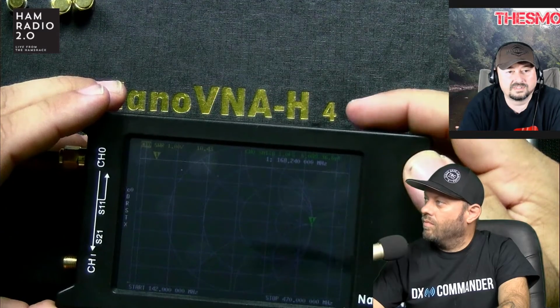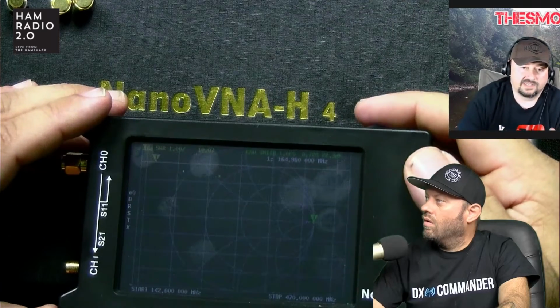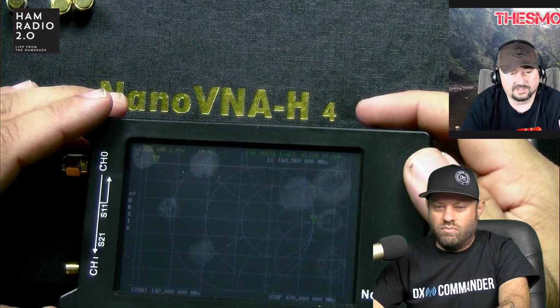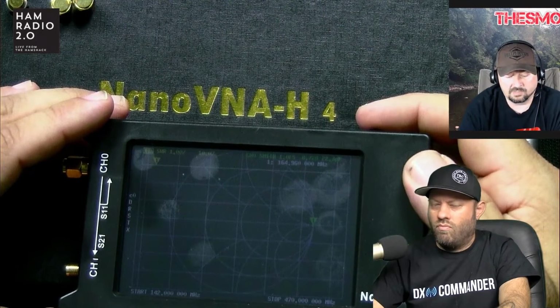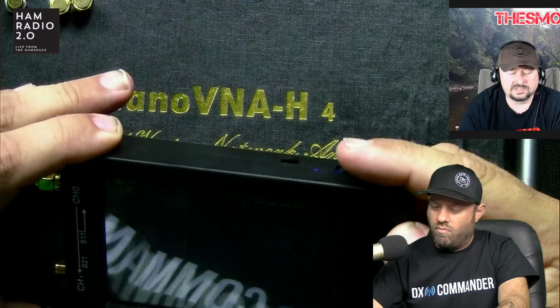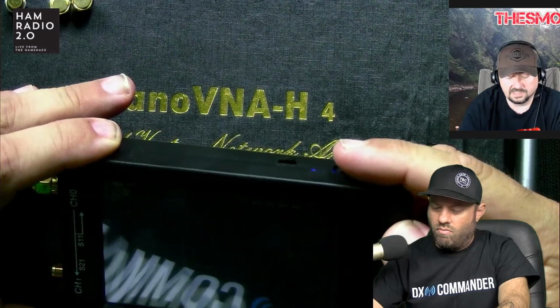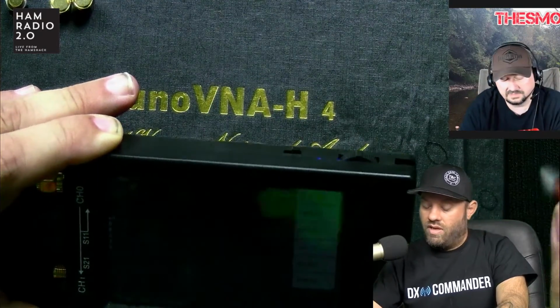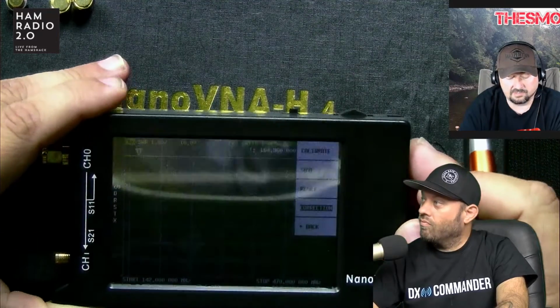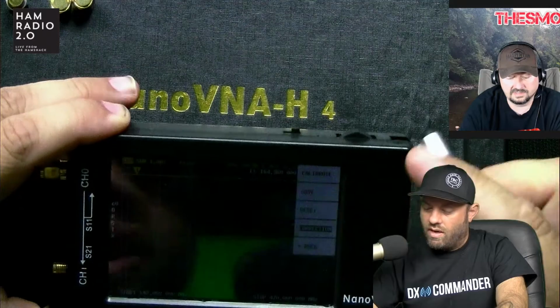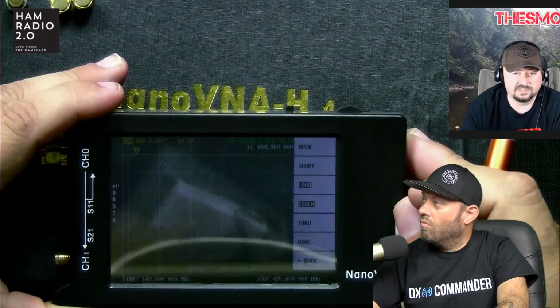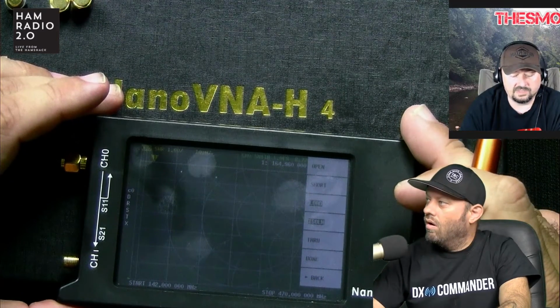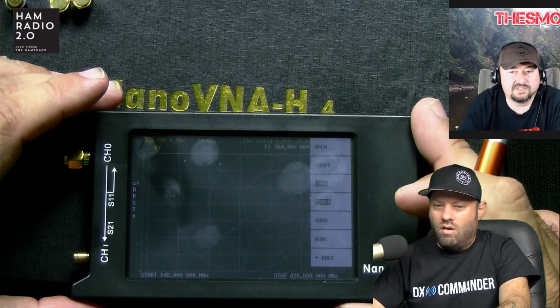Good. Now we didn't calibrate it at the device, so your readings might be different than what we got on the computer. To go through the calibration, and then also you can do a touch calibration in case your sensitivity on there is not good. Under the main menu, there's a button called Cal, C-A-L. You click that, and then there's a calibration set at the top. It says calibrate. And then it's the exact same thing that we did in the software. You go through the open, short, load, and you can stop there or do the isolation and through. Then you click done when you're finished, and it'll prompt you, and you can save it into, I think they call them slots, like slot 1, slot 2, slot 3.